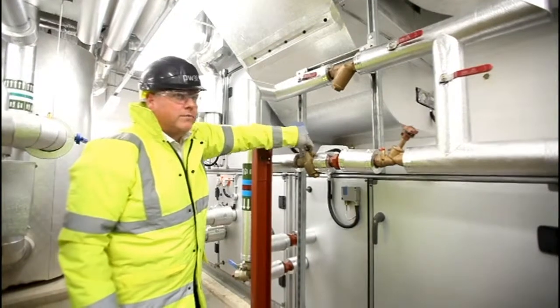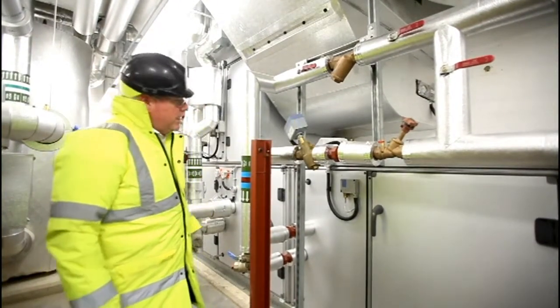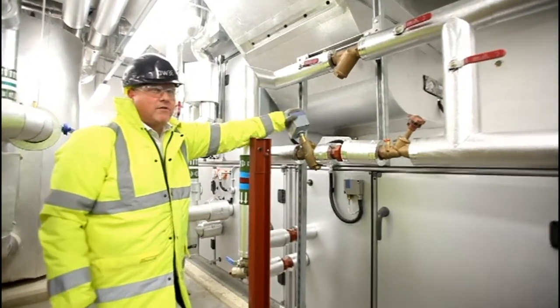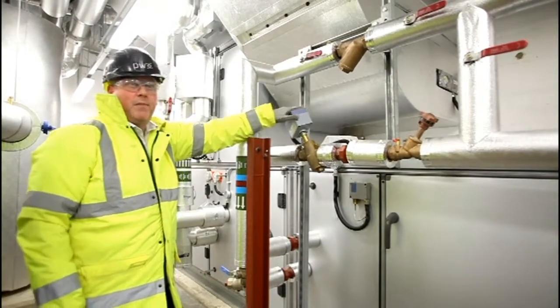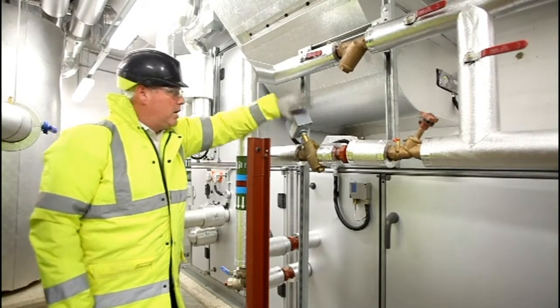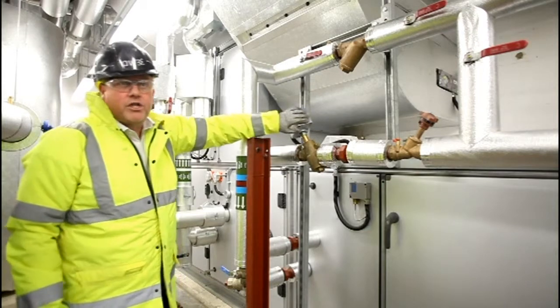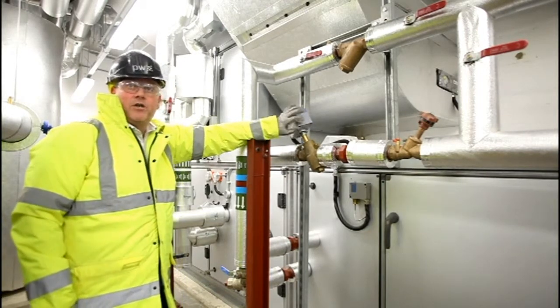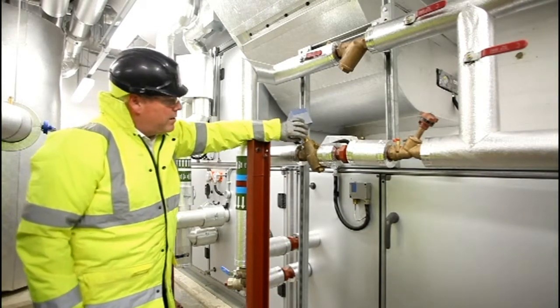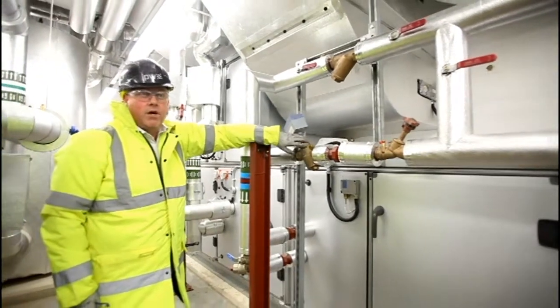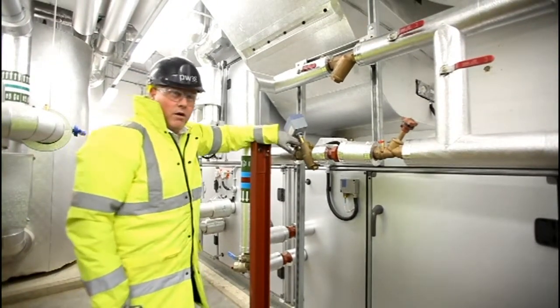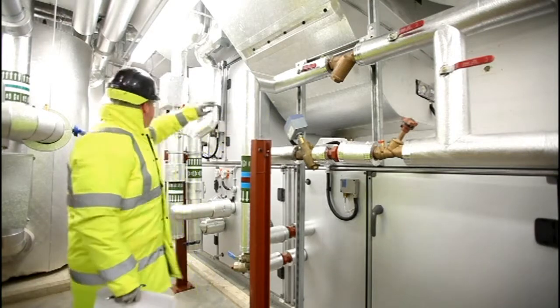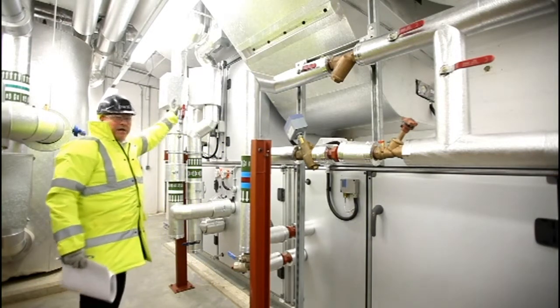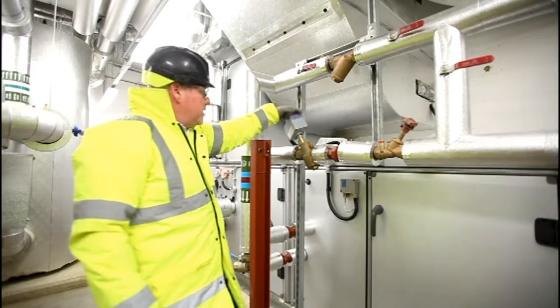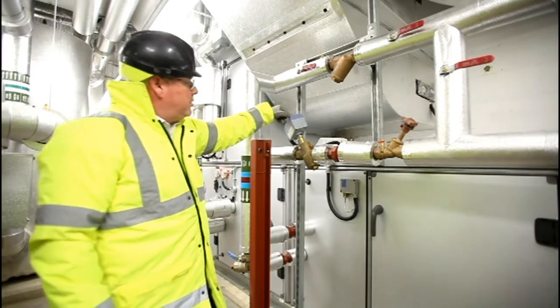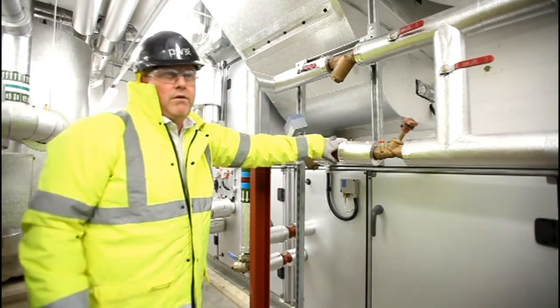The water that goes through the coils is controlled via motorised valves, again which are controlled by the building management system. You should never need to come and touch or adjust these. These are all preset throughout the commissioning process to allow the right amount of water required to heat the coil to a desired temperature. Again, the same on the cooling, a very similar device. Should never need to touch these. There's no forms of isolation, and it basically just goes up and down, lets an amount of water through into the coil.